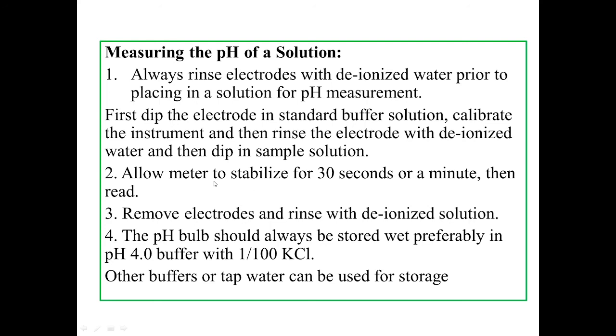Allow the meter to stabilize, say, for a period of 30 seconds to 1 minute, and then check the reading. Now your pH meter will display a correct and accurate reading. Note down the reading. Once the measurement of pH of the sample solution is over, remove the electrode from the sample, rinse it with deionized water, and clean it using a tissue paper.